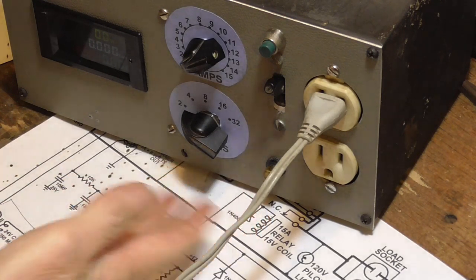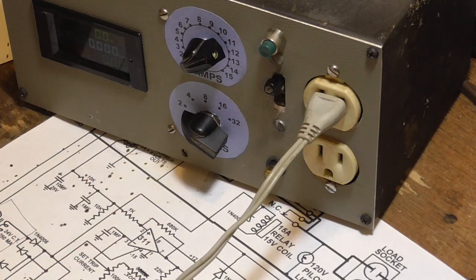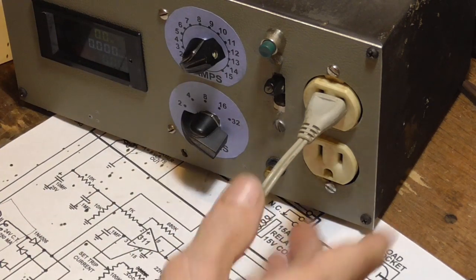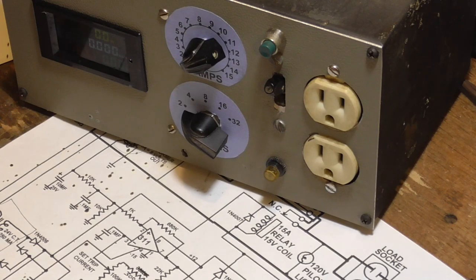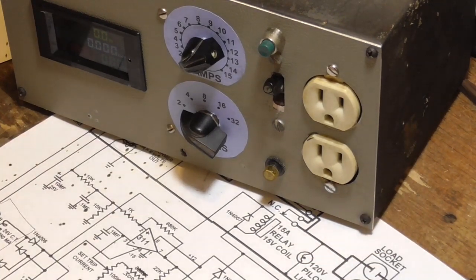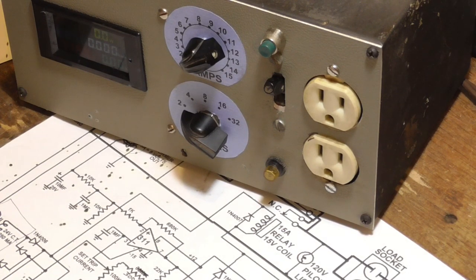Okay, so that protects our circuitry. You get a pretty good bang out of it because we have 2 cycles there of full 120 volts, whatever the line can put through before it shuts off. And I've measured it before, the short circuit current on my line in my lab is over 100 amps, that's where my big amp meter shuts off. So a dead short in this room is 100 amps for about 3/10 of a second before the main house breaker blows. But this goes ahead and protects our line so that we can't blow the main house breaker, and we don't run 100 amps for any length of time through our wiring.